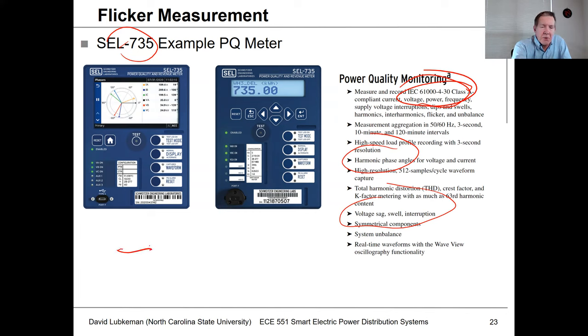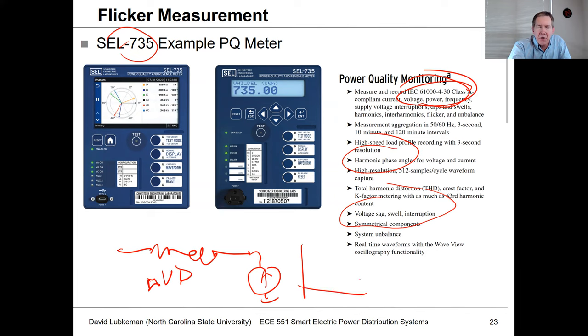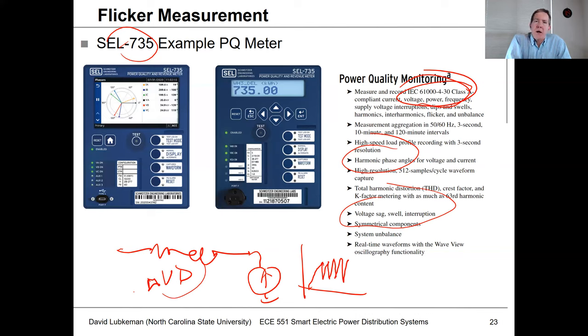Where this is pertinent to PV is that PV looks like a current injection, and what you get as a result of current injection is a voltage drop. However, a lot of DER sources are intermittent — you get some cloud cover and the PV output oscillates, causing a change in the current injection, which causes oscillation in the voltage changes. This is kind of the flicker. Not only do you get this with PV, but you also get this with wind to a certain extent as well. This is one thing we look at — these flicker numbers — when examining the impact of PV and deciding whether we can afford to add an installation to a distribution feeder.